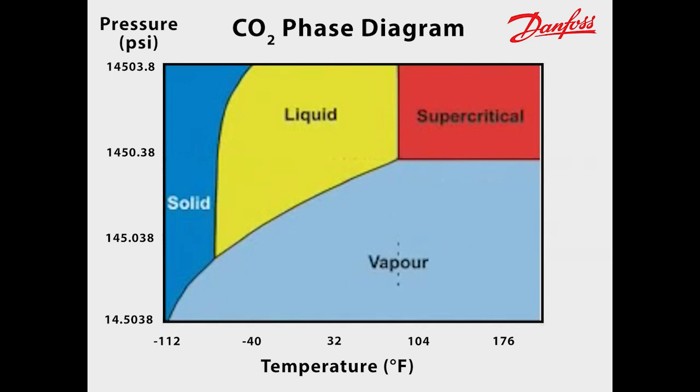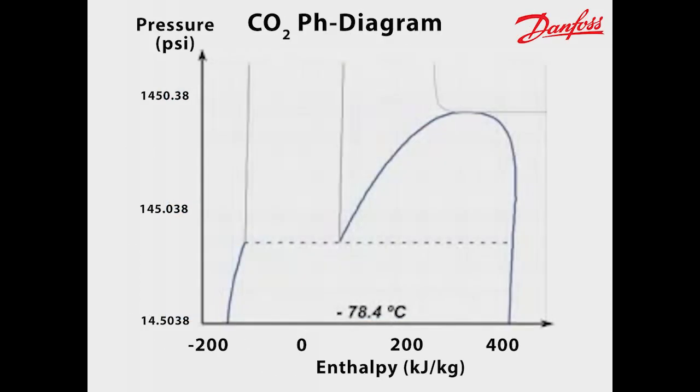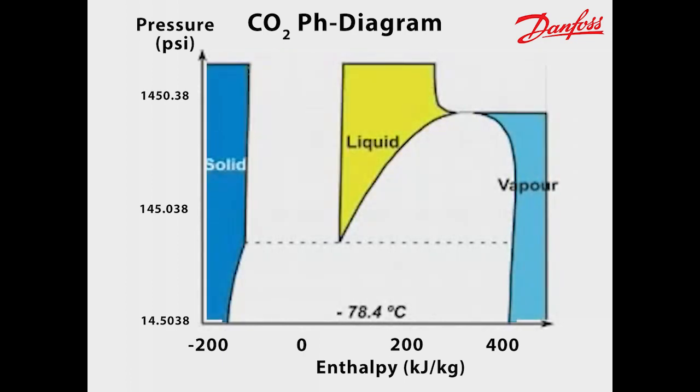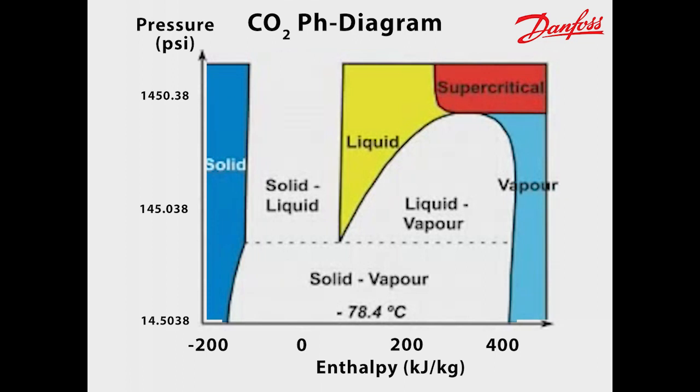The pressure enthalpy diagram is typically used for refrigeration purposes. For CO2 applications, this diagram must be extended to include the solid and supercritical phases. The colored areas indicate the different phases of CO2, namely vapor, liquid, solid, and supercritical. The triple point is here, and the critical point is here.